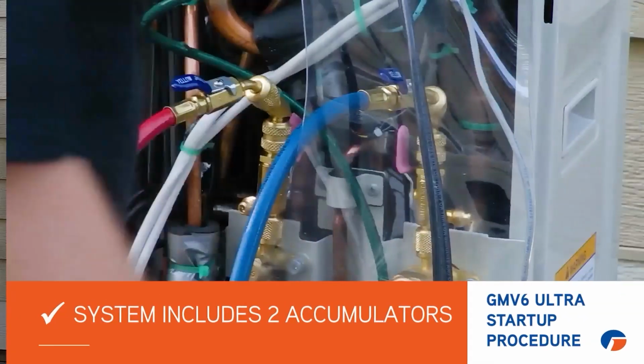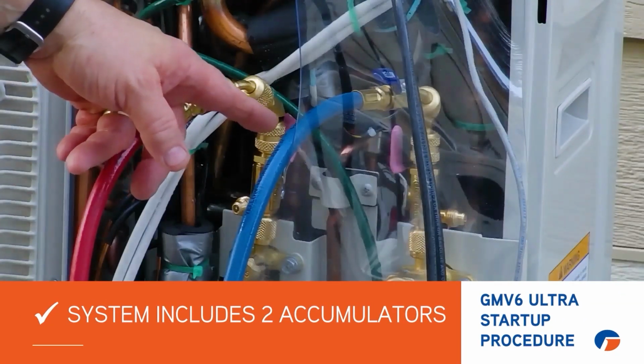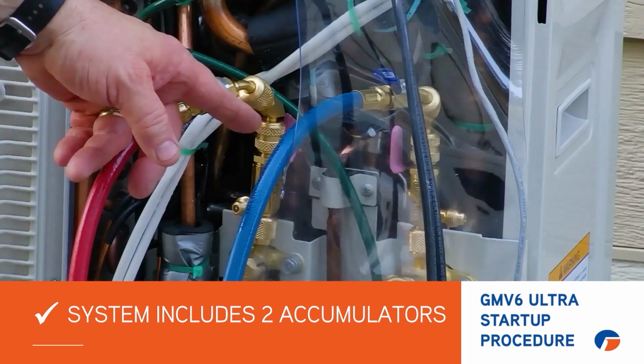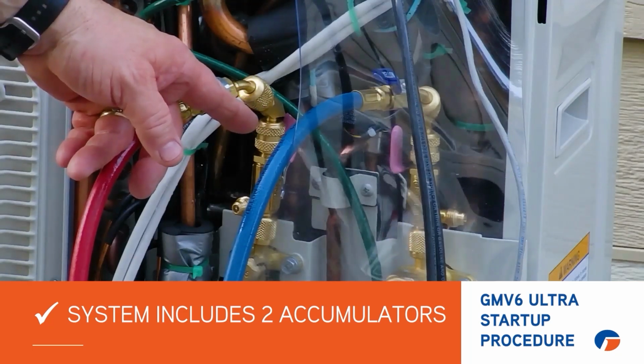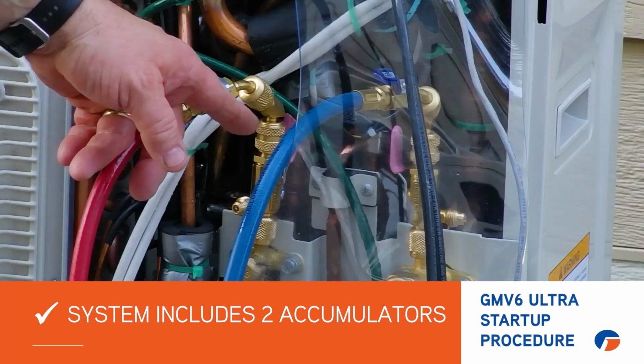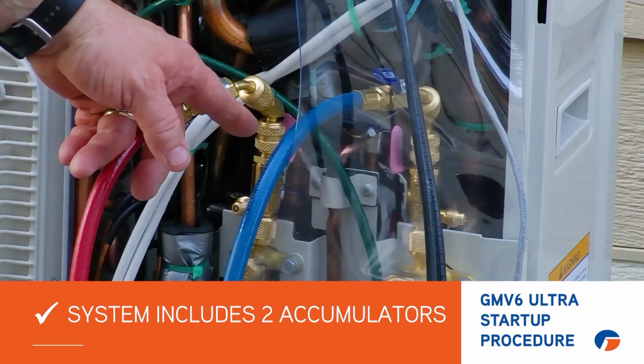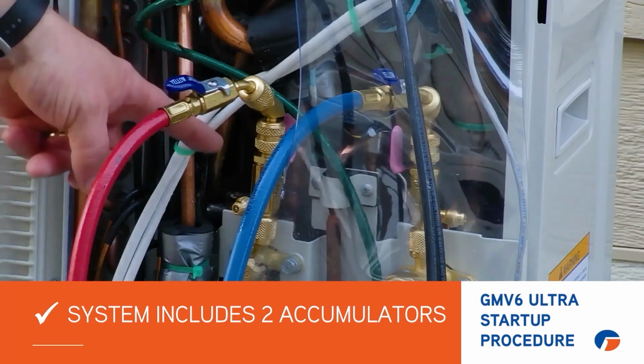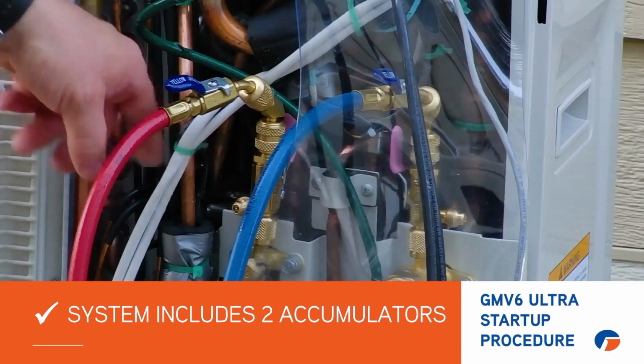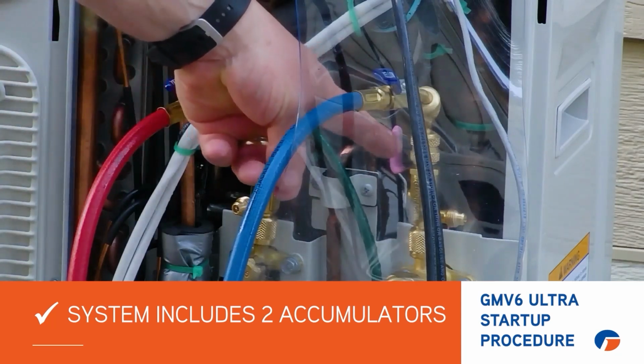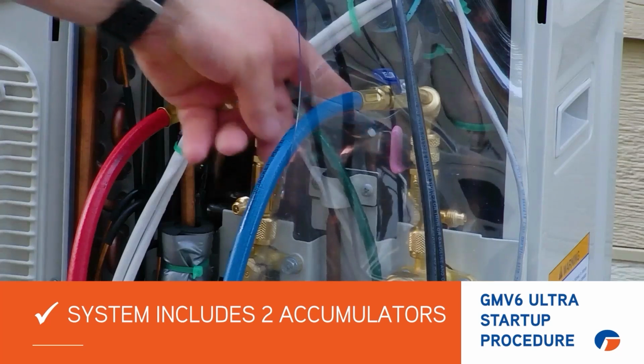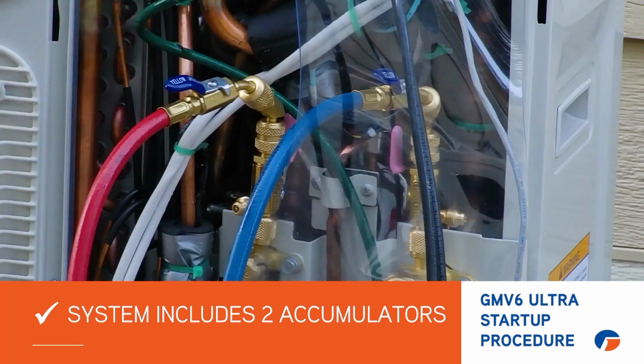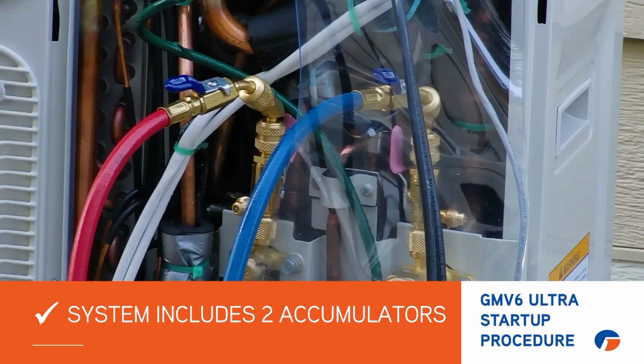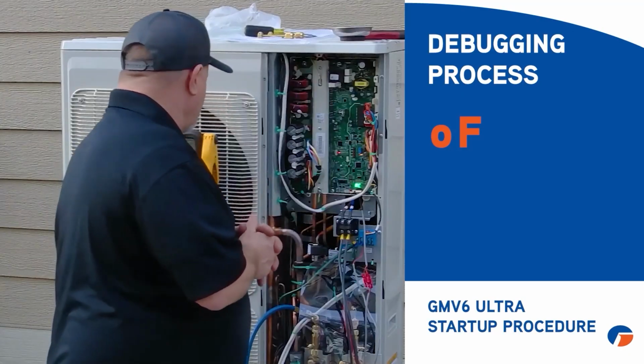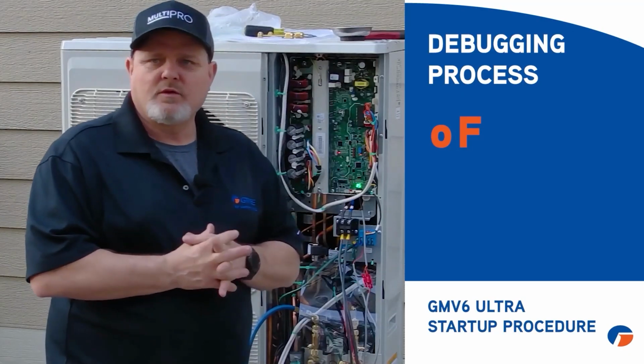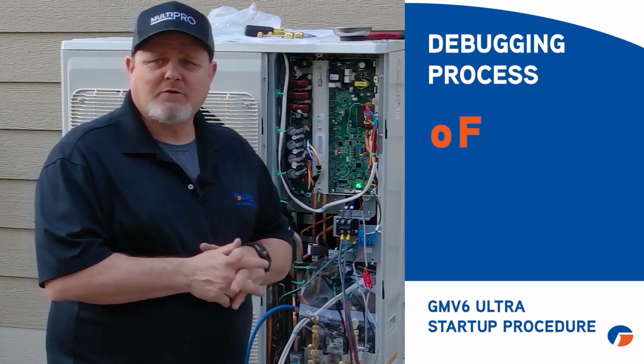Don't worry about putting liquid in that low side, because you've got 2 accumulators in this unit. Even if you dump liquid in the low side, when it goes to start up, it's got to get through those accumulators before it would slug the compressor. So you're good to go. Just dump your charge in both high and low side, and then you can isolate your tank off like I've got mine isolated off, because whatever's left in my hoses, I'm going to bleed into the machine. That's it. We're going to let it do its thing now, and I guess we'll button it all up after it's run for 50 minutes.